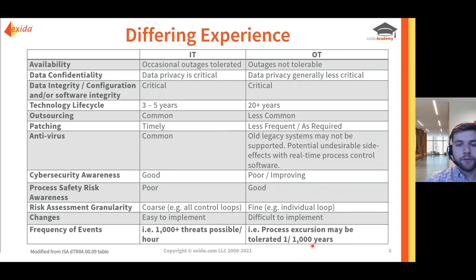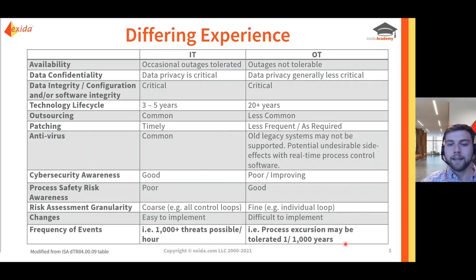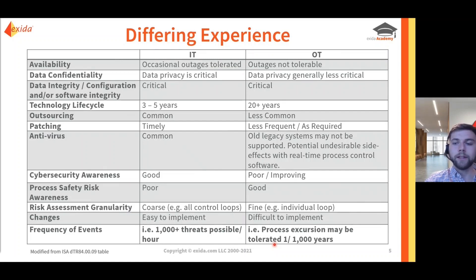The last interesting area is terminology. The IT and OT groups may have a pretty significant separation in their standard terminology. For example, it wouldn't be uncommon for an IT resource to talk about thousands of possible threats per hour, given the very high frequency of untargeted and unskilled attacks on internet-connected systems. Alternatively, an OT group might discuss a process excursion and say a high temperature scenario going above a control set point is only tolerated once in a thousand years. That's six orders of magnitude difference, so we really want to work on breaking down these differences in experience and understanding any terminology and other core differences that need to be overcome.